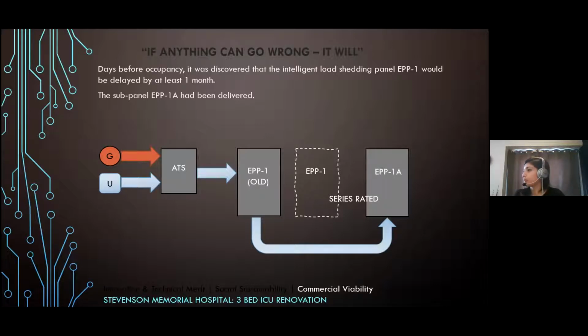So what we came up with was installing an isolation transformer. An isolation transformer limits the maximum fault current that flows downstream of it. So with this isolation transformer, our system was considered safe in our eyes. It cost us an extra $5,000 and it took 4 days into our schedule, but it was still a better option than having to wait an entire month for that main panel to arrive. And then we had to disconnect the new AC unit to make sure that we didn't overload our generator, which was fine because we didn't need the AC unit in the wintertime.